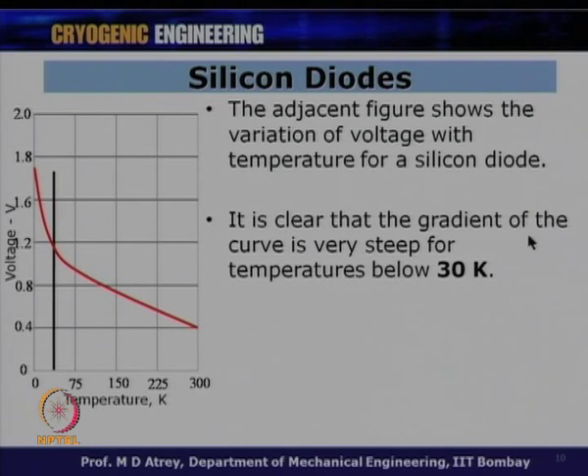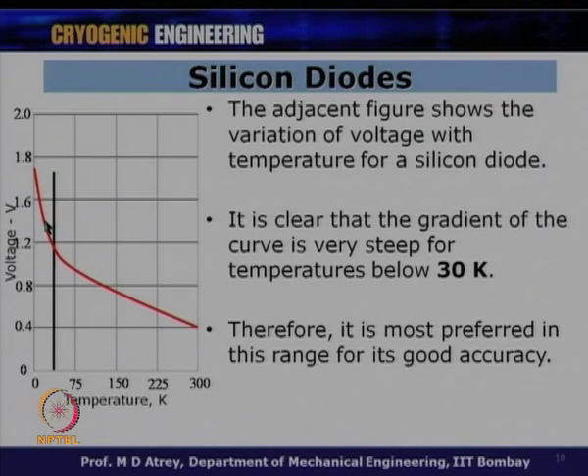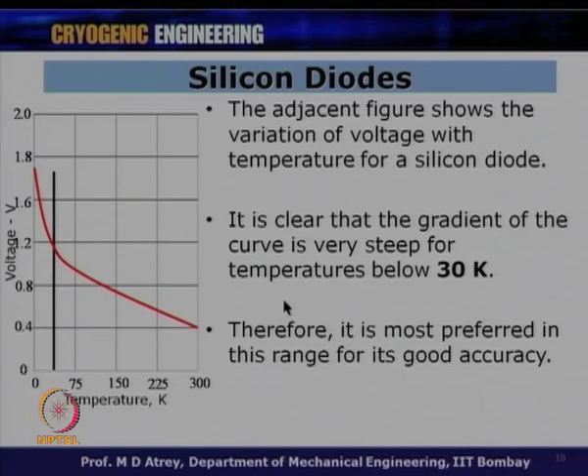The gradient of the curve is very steep for temperatures below 30 Kelvin, which means sensitivity increases significantly there. Therefore, silicon diodes are most preferred below 30 Kelvin for good accuracy compared to PT100 or thermocouples. At lower temperatures, silicon diodes are always preferred — at 4.2 Kelvin or liquid helium temperature levels.